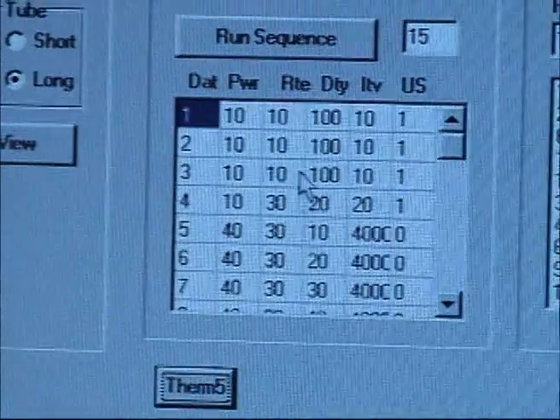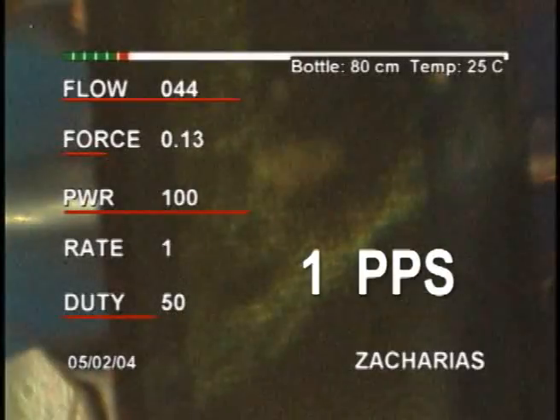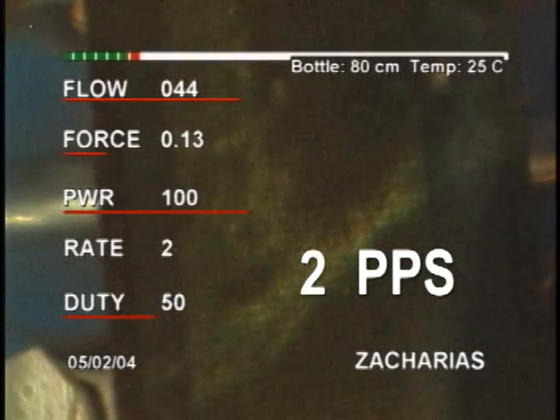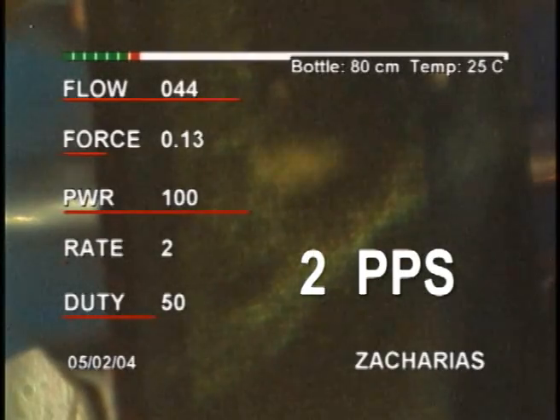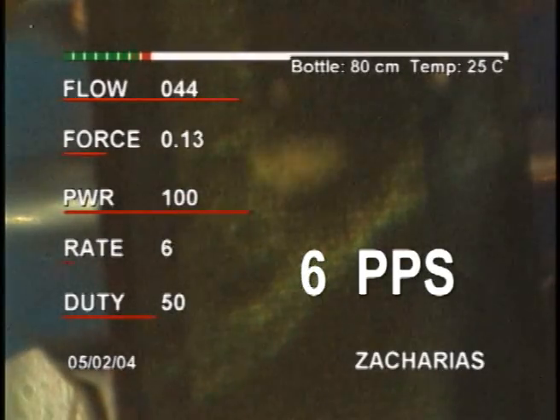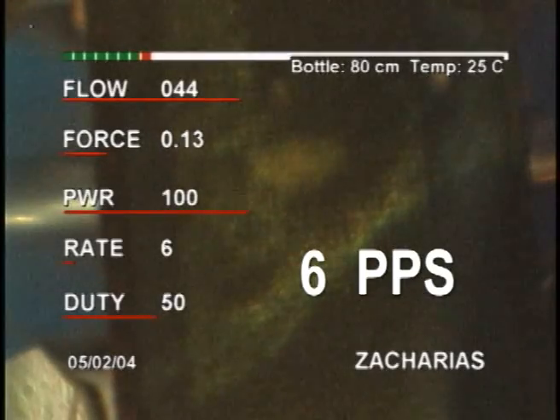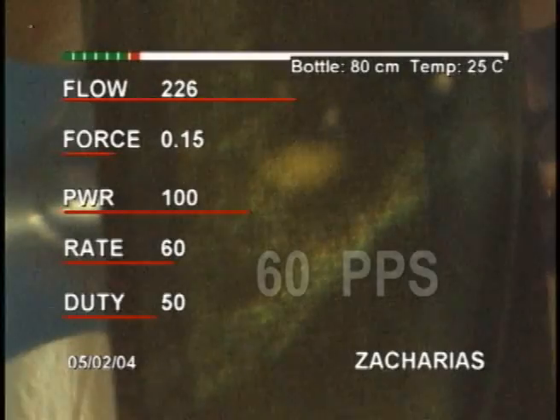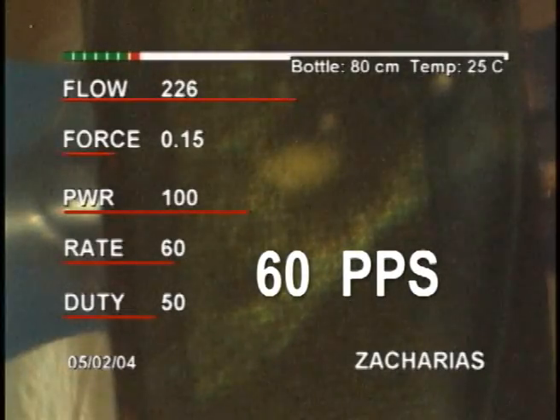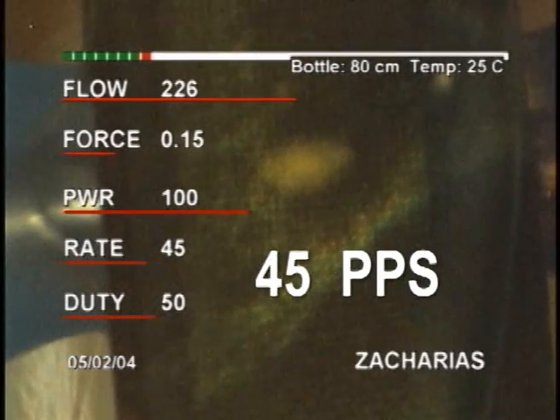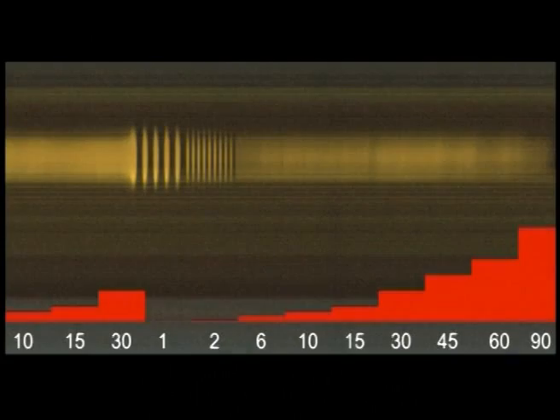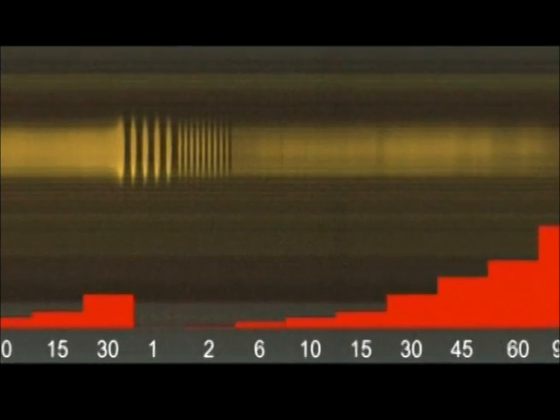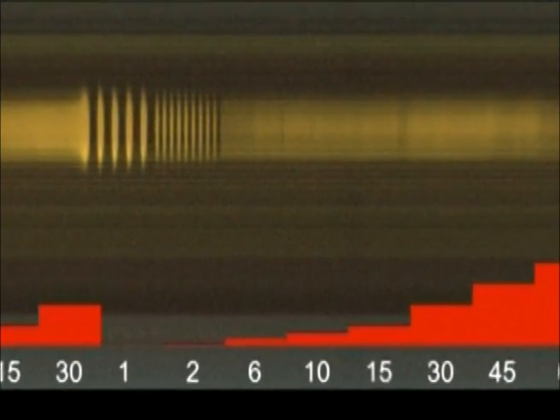With a model incision, we determined that using standard pulses in the range of 1 to 6 pulses per second, temperature would rise and fall following the on-time and off-time of the US pattern. With repetition rates of 10 pulses per second and above, and totally extending into the hyperpulse range, temperature oscillations fused into a steady temperature. This made full sense from a thermodynamics perspective.